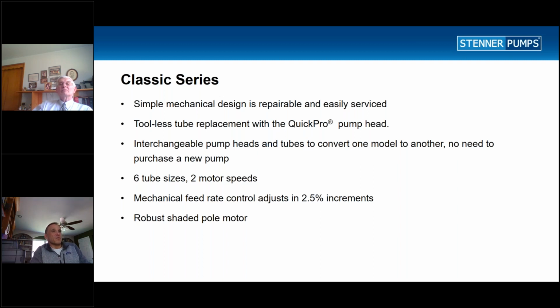What makes the classic pump design so unique is that we have the QuickPro head, which will allow you to engage and disengage the rollers by using the cover on the pump housing. We have 6 tubes, 2 motor speeds, and I'll explain the motor speeds a little later when we talk about the gearing. You can interchange pump heads to convert from one pump to another. So if you're using an old style classic pump with screws in the cover still and the old roller, you can purchase a new QuickPro housing and mount it on your Stenner pumps that use the old style heads. One thing on the pump is that you have a 2.5% increment adjustability on that too.